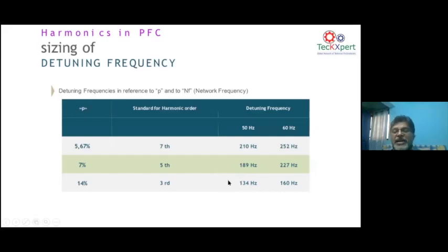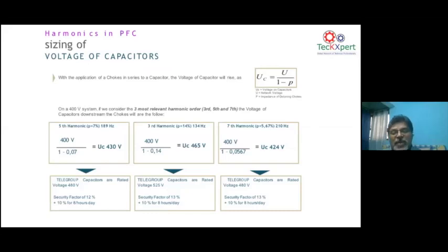Now, if you have third harmonic current in the system, if third harmonic is 150 cycles, you use a 14% reactor, and by using a 14% reactor, you are detuning the circuit away from the third harmonic current to 134 hertz. At 134 hertz, there are no harmonics present. So by detuning a capacitor bank, you are ensuring that the capacitor bank is protected. But the only thing is, when you detune, you have to always make sure the capacitor that you use has sufficient voltage rating to take care of the detuning reactor.